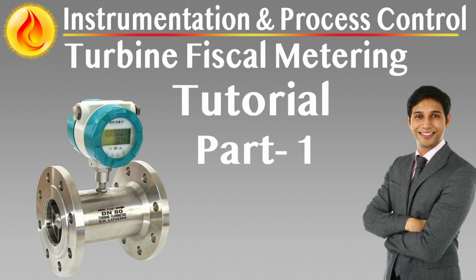Instrumentation for process compensation. Each metering run includes a pressure transmitter and pressure gauge to measure local line pressure, along with a temperature transmitter and temperature indicator housed in independent thermowells. These values are used by the microcomputer to compensate for temperature and pressure effects on fluid density, enabling accurate mass and corrected volume computations.